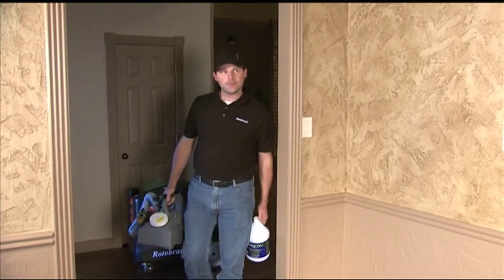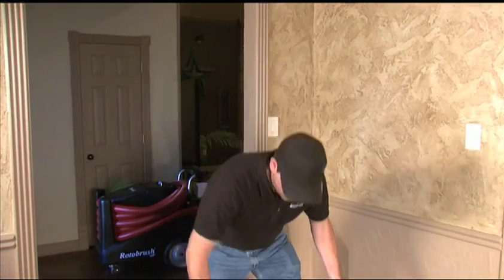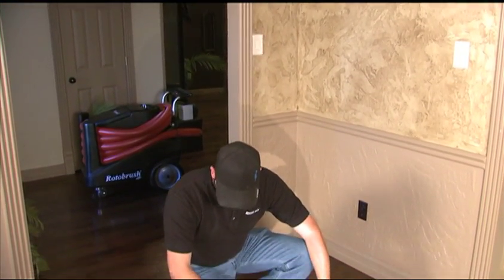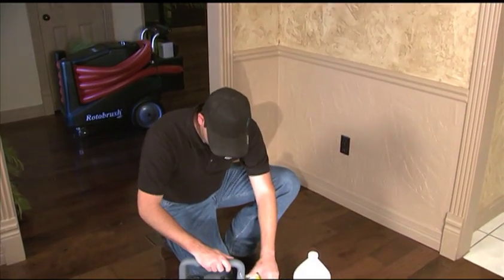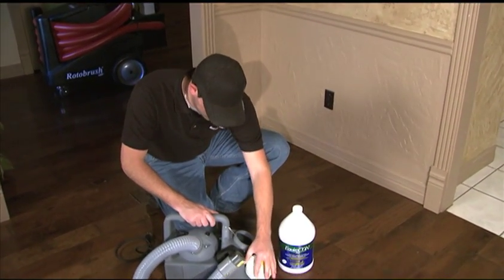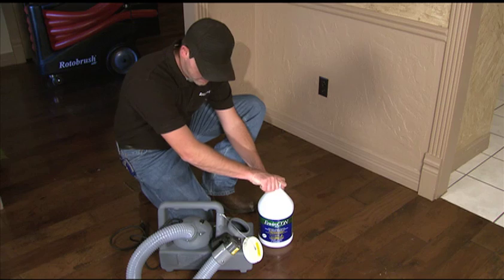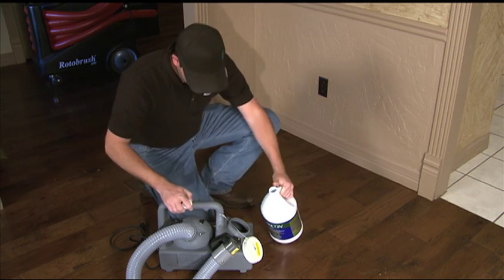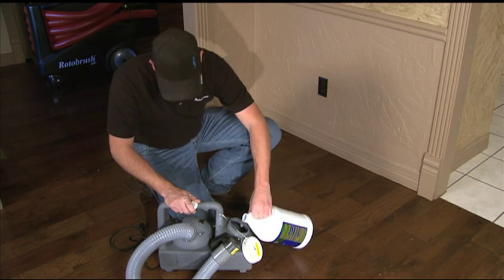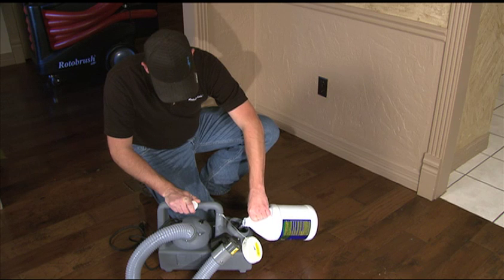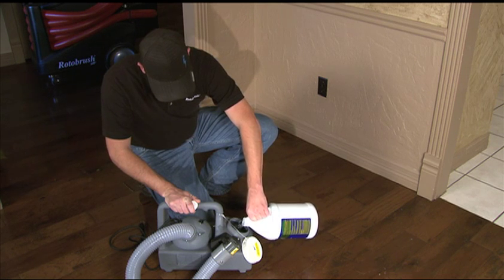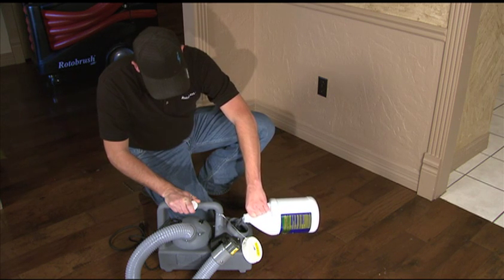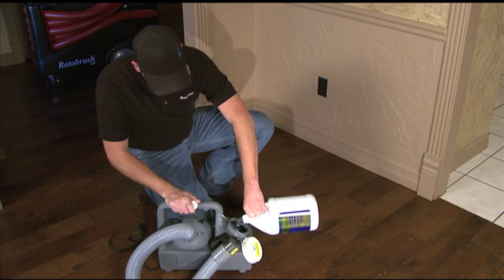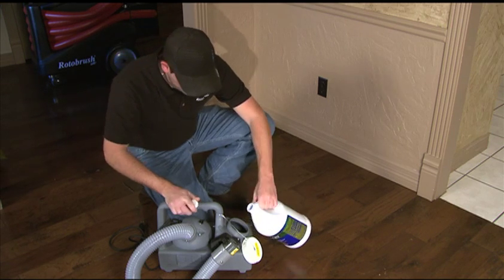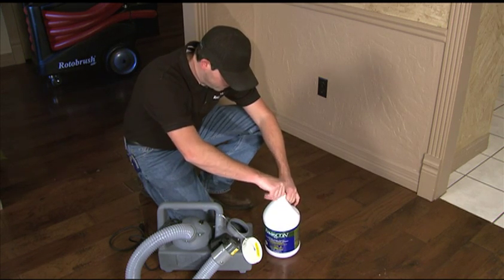Okay, we're on to fogging. Typically what we use for fogging is EnviroCon. This is an antimicrobial fungistat deodorstat that's ready to use. You don't add water and there is no mixing. All you do is simply pour this into the fogger. Typically, you want to put about 1/3 to 1/2 gallon in. If you put the whole gallon in, you'll just have to carry around the weight, because each gallon is enough for about 10 to 12 jobs. What you're going to do is tighten down the lid, and then you're ready to fog.